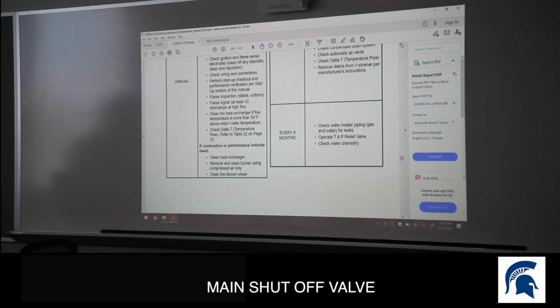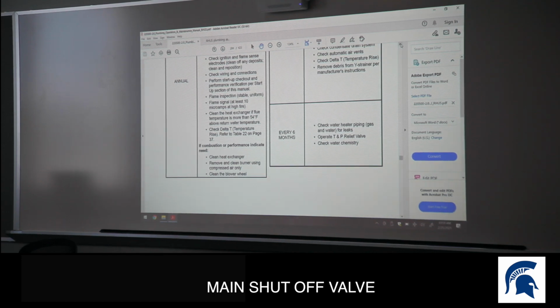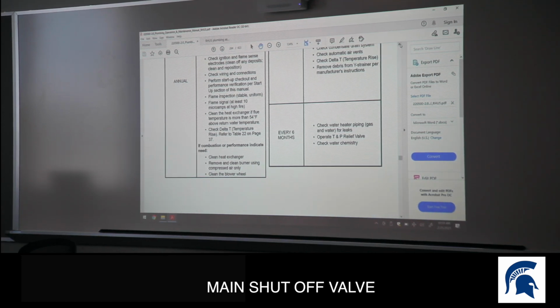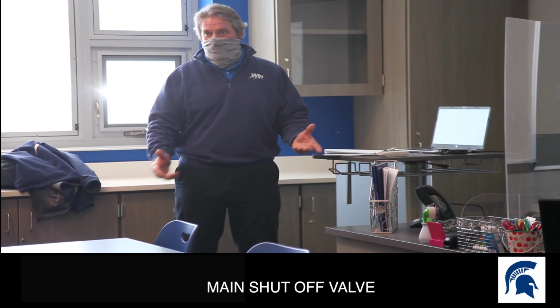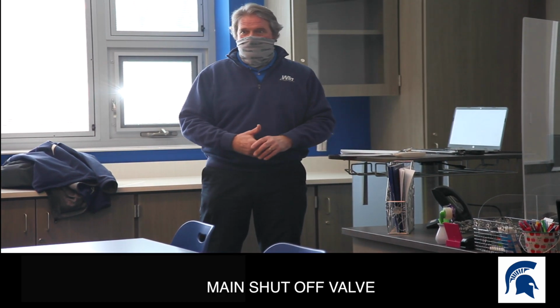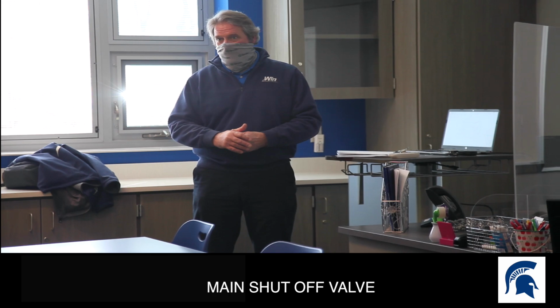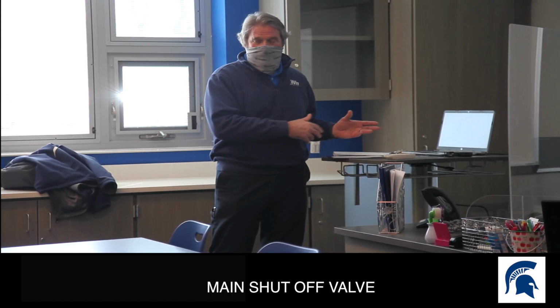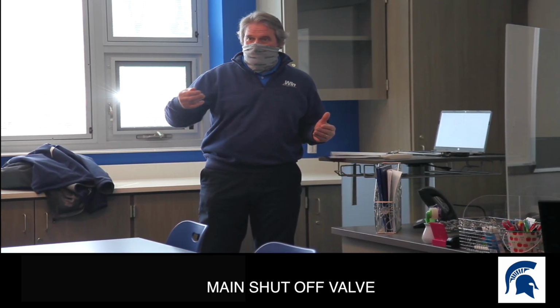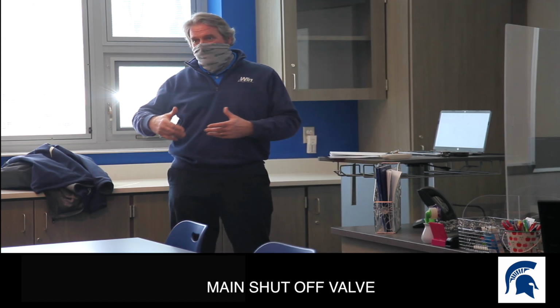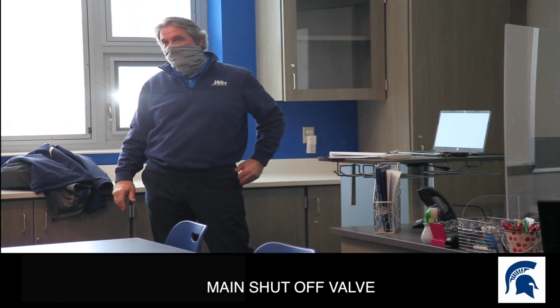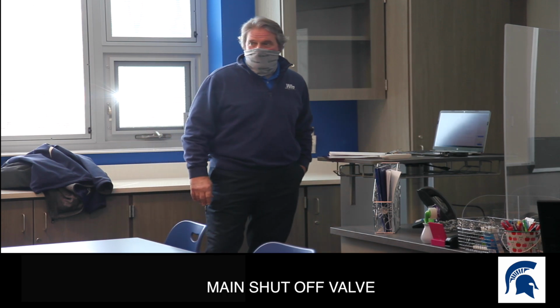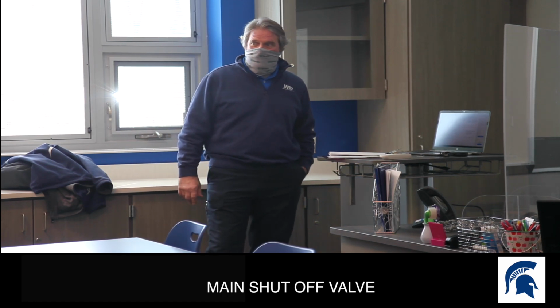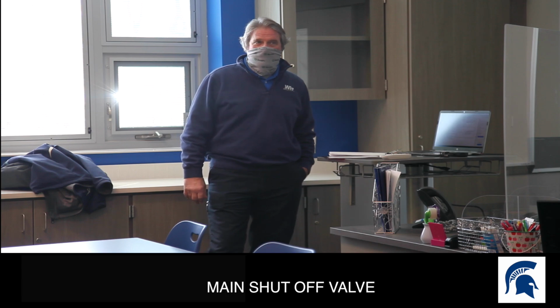And technically, this is just a hot water heater, okay? Because it's in an open system that's heating domestic water. If it was in a closed system with your radiant floor heating or some kind of heating system, then it would be considered a boiler. This is still considered a hot water heater, but over 200,000 BTUs in the state, they want to treat it like a boiler. What's the temperature on the water coming out? Whatever you need it to be. Or what's it set at? So it's set at 140.